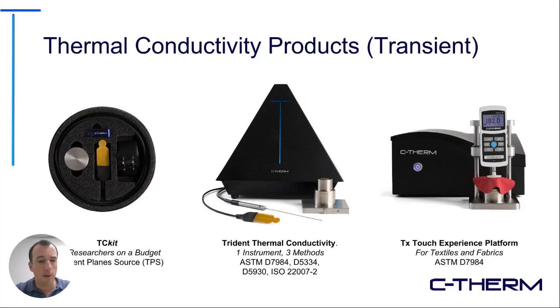The needle probe in the middle there, the stainless steel needle. This is our most robust sensor. It's sheathed in stainless steel. It's very robust. It's really designed for polymer melts in very sticky situations where you might be worried about the material bonding to the sensor. So Sarah will highlight its use as part of the response to measuring polymers. Certainly when you get into polymer melts, the needle is a great addition.